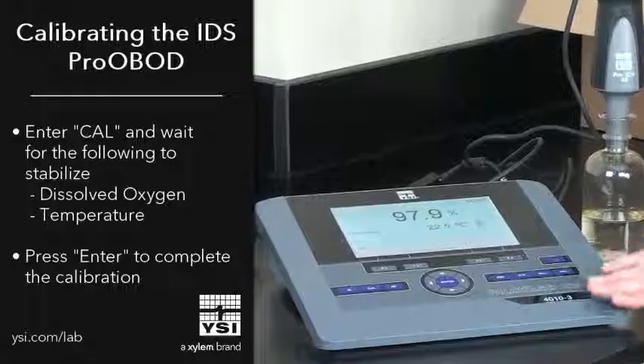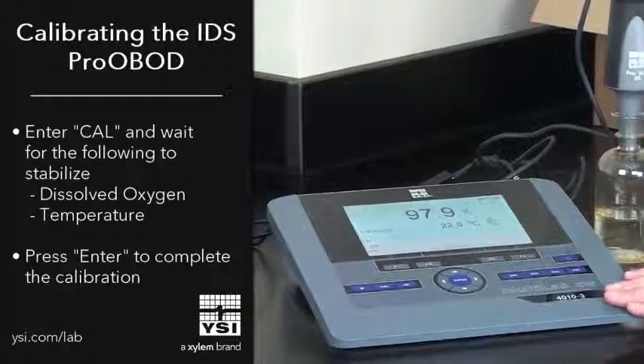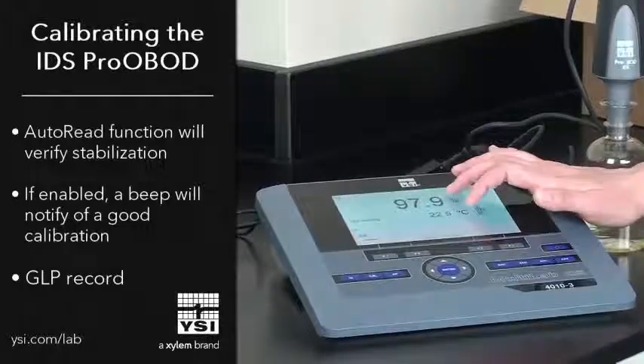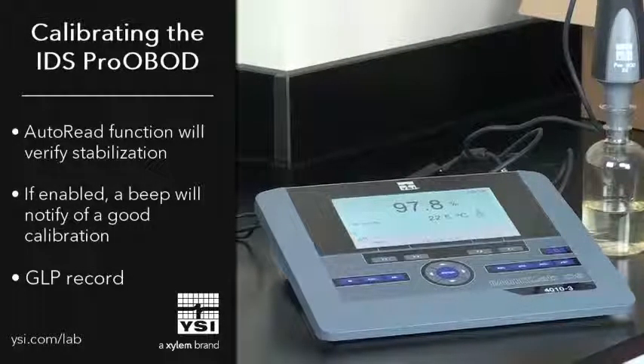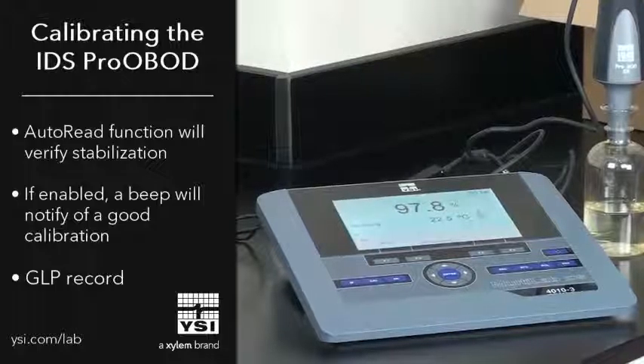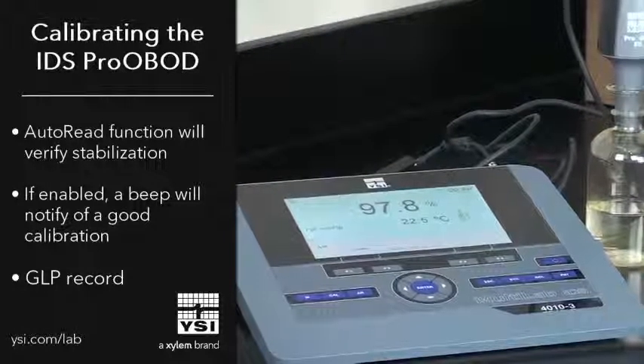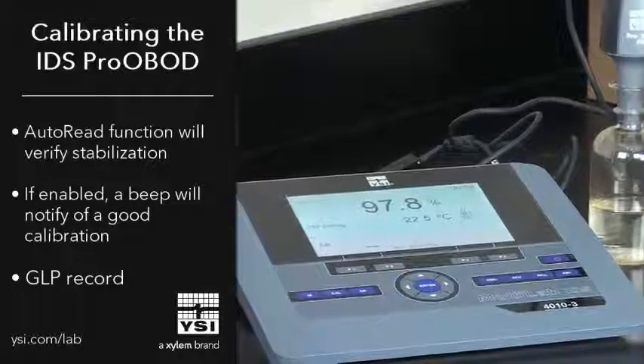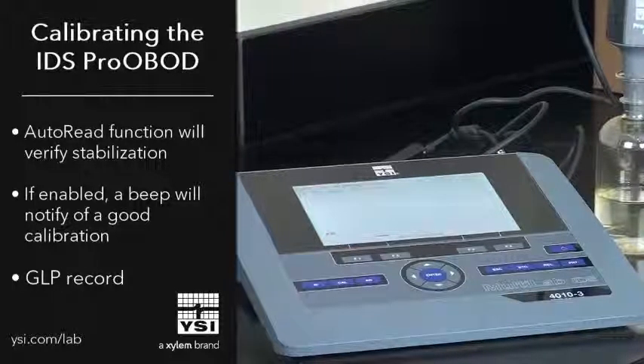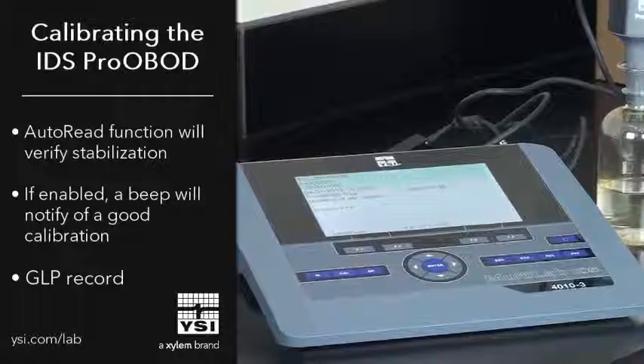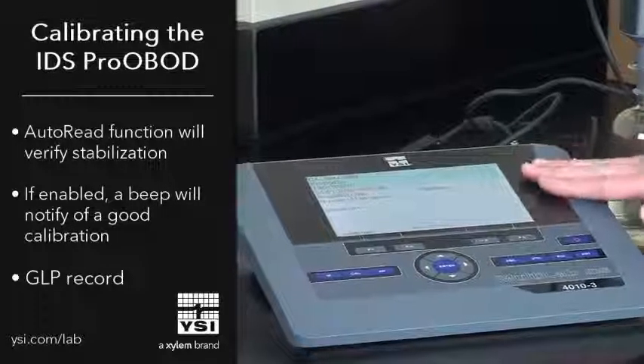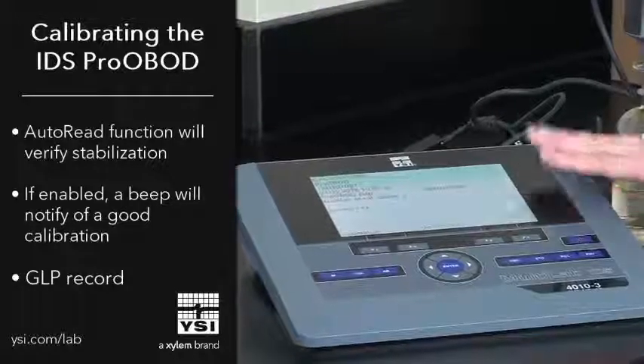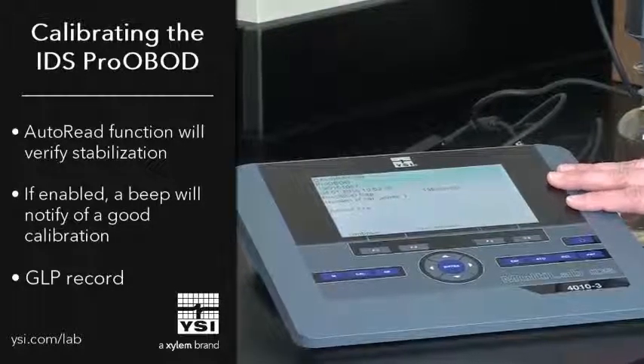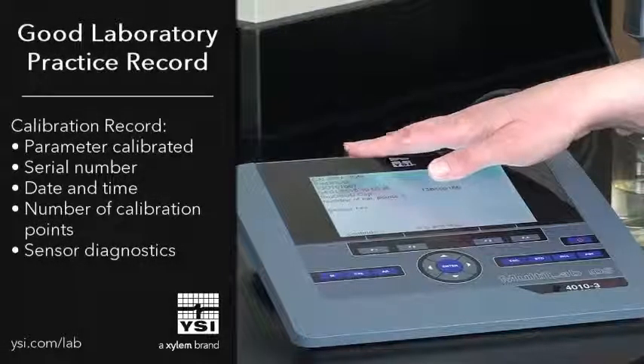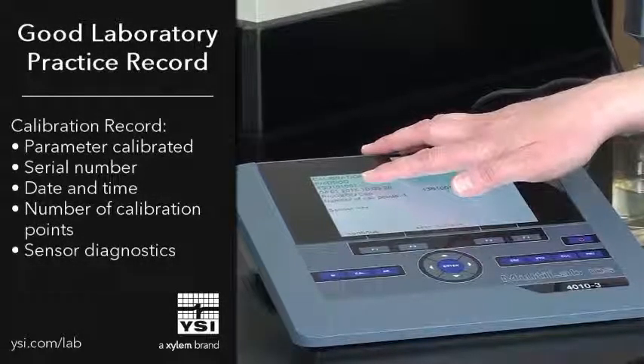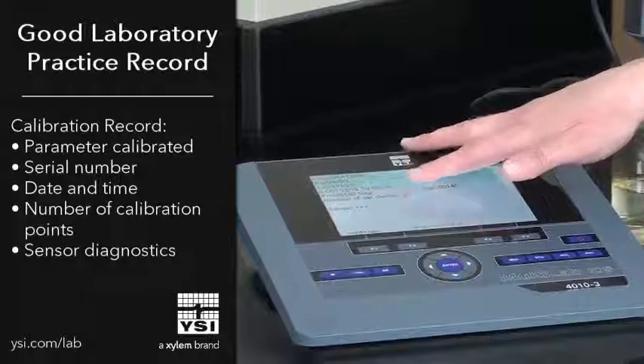Once the dissolved oxygen and temperature measurements are stabilized, we're going to go ahead and press Enter to complete the calibration. Now the instrument will double check this for you and will perform an auto read function to determine both measurements are stable and ready for calibration. Once the auto read function is complete, the instrument will beep, confirming a good calibration, and will show you a record from the GLP file, the good laboratory practice file that stores the calibration records in the instrument.